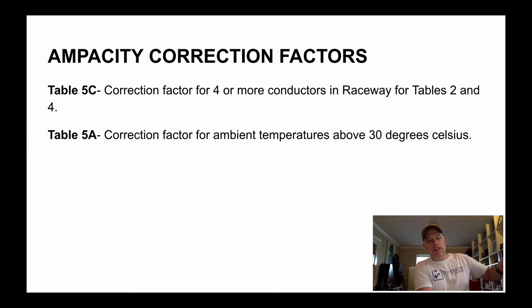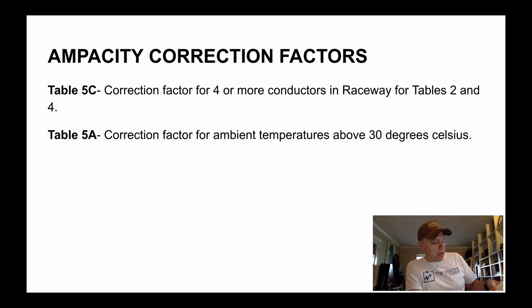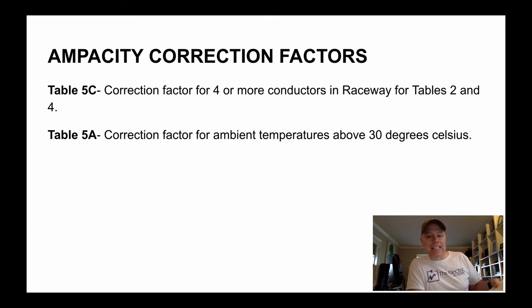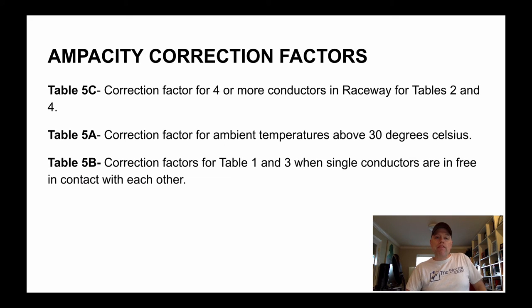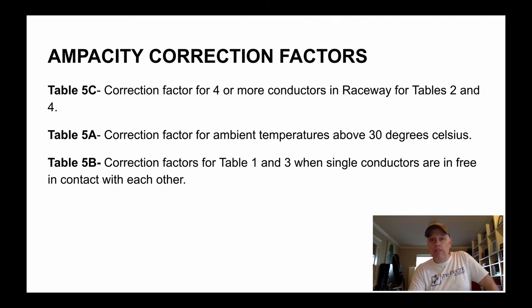Table 5A is referred to in 4-004 subrule 7, item B, item I, and it covers ampacity correction factors where conductors are installed in an ambient temperature exceeding or anticipated to exceed 30°C. Table 5B covers correction factors for tables 1 and 3, where single conductors are in free air and in contact with each other. I don't go over table 5B in the examples because I've rarely used it in real life — if you have, please leave a comment below.